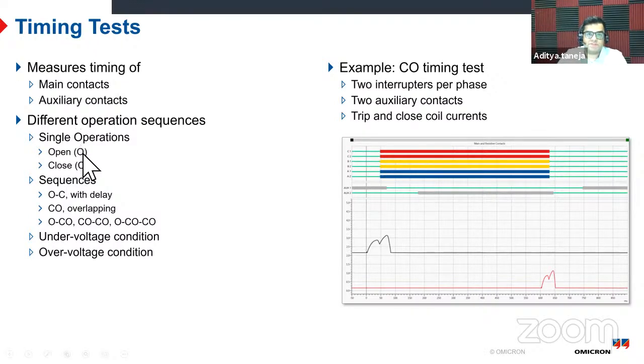And then there are a lot of sequences. So a breaker is expected to do open, close, close, open, and more sequences. And trust me, all of them are important and should be done at least during the inspection test, because some problems which you do not see in normal tests, you can see in these complicated sequences, because here it really stresses the mechanical part of the breaker to its limit, and if there is any softness in the mechanism, it will become clear here.